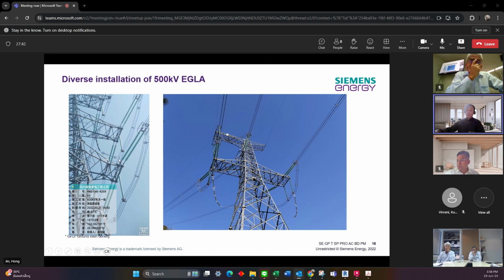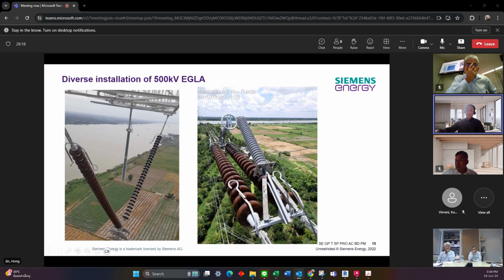So in those areas, if you permanently have such strong wind force, to avoid such a swing of the conductor or the jumper conductor, we have used one long rod insulator to hold both electrodes here. One side is from high voltage, the other side is from the surge arrester. And this is the gap distance here. It will be fixed by the long rod insulator. With this standard design, we can use one design for all different towers. Not like this one. This one is always a customized design.